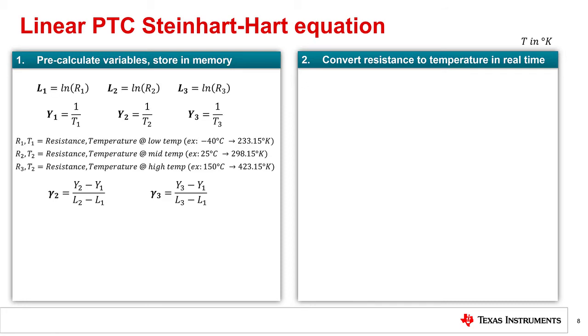Using the lookup table provided by the manufacturer, you can calculate L1, 2, and 3 as well as Y1, 2, and 3. Keep in mind, this linear PTC version of the Steinhart-Hart equation uses temperature in degrees Kelvin, so you need to convert from Celsius to Kelvin first. In order to accurately characterize the resistance to temperature curve, you need to pick three points across temperature.